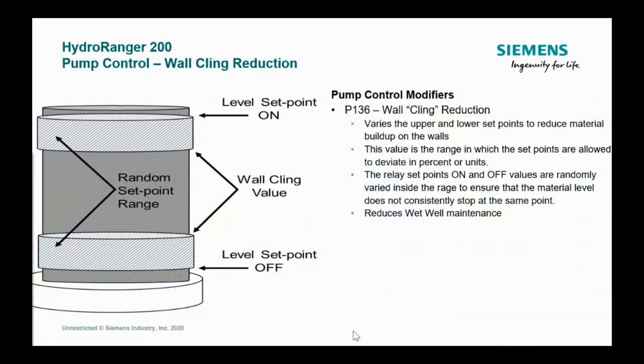There's something that's called wall cling reduction. This is specifically for the wastewater guys. That's where we see it most often. Parameter number 136 is one that you would use, or guess what? It's called wall cling reduction in the Hydroranger HMI. Basically, what you do there is you're going to randomize the set point. So let's say your pump comes on at 10 feet, okay? And if it always goes up to 10 feet and then always pumps down to the same point, eventually you get kind of a grease ring, or you get a buildup right there on the side of your wet well.